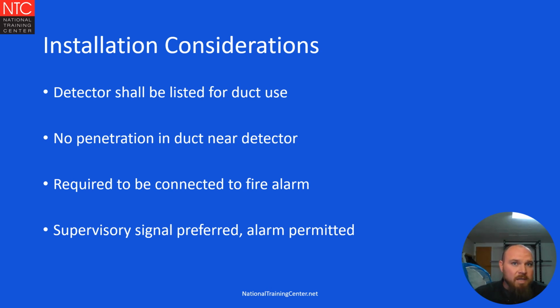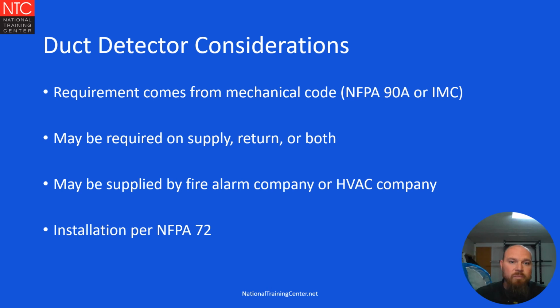If we have duct detectors, they have to be connected to the building's fire alarm system. So if there's a fire alarm system and duct detectors are there, you're going to have them connected. Most duct detectors send a supervisory signal. However, in some instances, alarm is permitted.